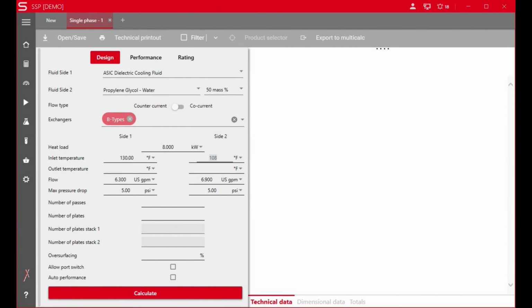They get you close enough for the tool to work. Now, when entering the values, it's important to lock down the numbers we really can't change. This would be the power or heat generated by the miners, the maximum temperature of the fluid coming off the miners and going into the heat exchanger, and the dielectric fluid flow through the miner tank.